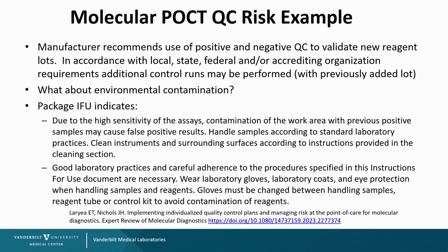So clean instruments and surrounding surfaces according to instructions provided in the cleaning section. Good laboratory practices and careful adherence to procedures specified in the instructions for use document are necessary. Wear gloves. Use laboratory coats. Eye protection when handling samples and reagents. Gloves must be changed between handling samples, reagent tube, control kit to avoid contamination. So we took this as pretty high risk, that we could get false positives out there.